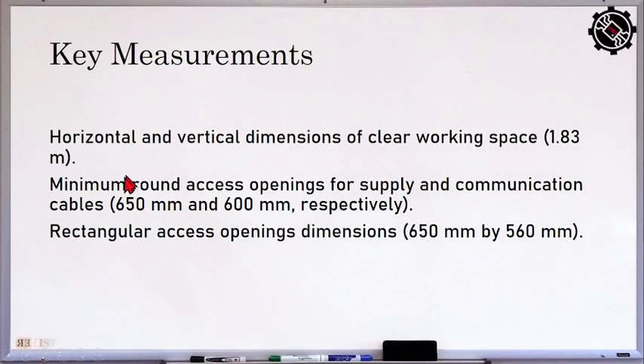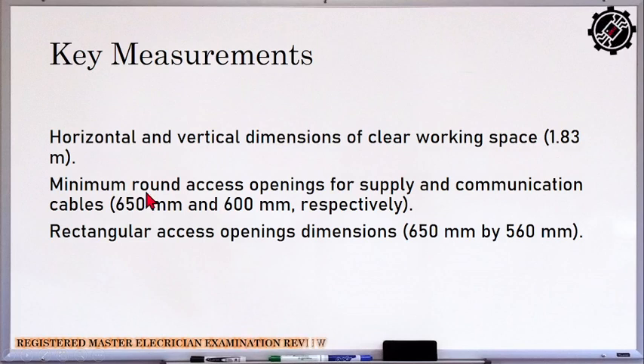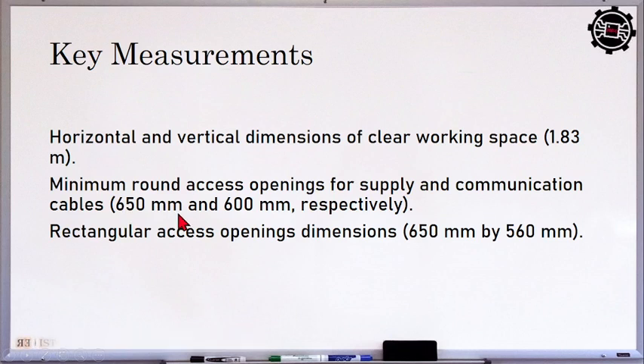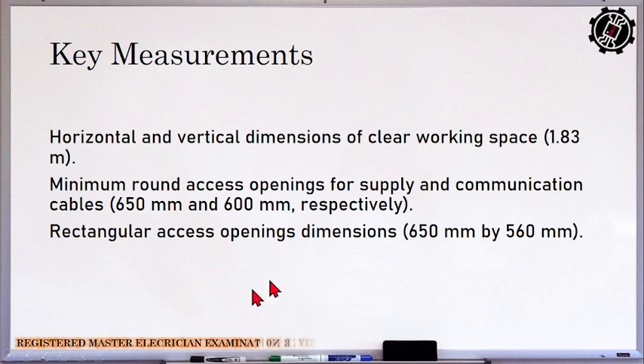Okay, so measurements. The horizontal and vertical diameter of clear working space on manhole is 1.83 meters. The minimum round access openings for supply communication cables is 650 mm and 600 mm. So 650 ang kanyang diameter for supply, 600 mm for communication. That is for round na mga manhole. If rectangular access, the dimension, the length is 650 mm and the width is 560 mm.